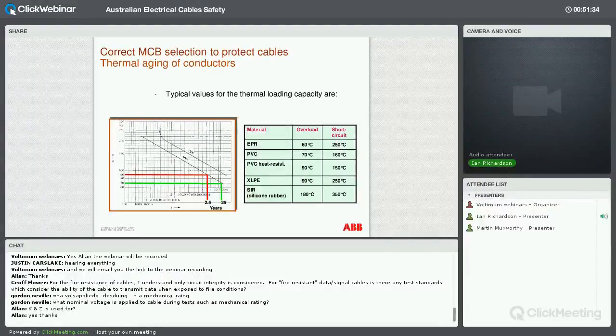One thing which certainly opened my eyes when I first saw this graph on the left-hand side is, let's say, a typical graph for a PVC V70 cable. Cables are generally rated for a 25-year lifespan. So running at its 70 degrees at its full current, the cable has a life expectancy of 25 years, as you can see from the green intersection there. Let's say we allow this cable to run at 90 degrees, so only increase the operating temperature by 20 degrees. According to the graph, your life expectancy will reduce to 2.5 years.